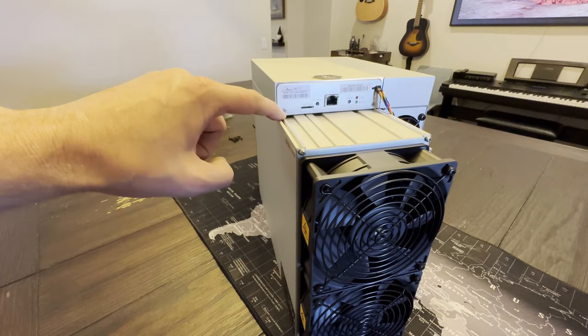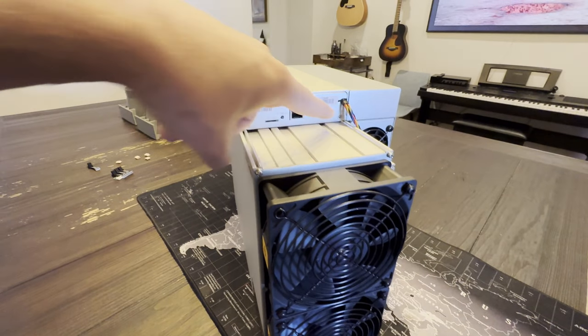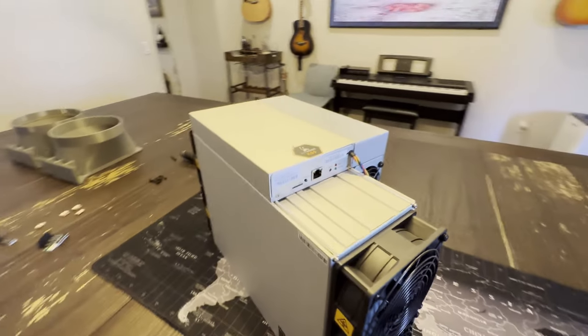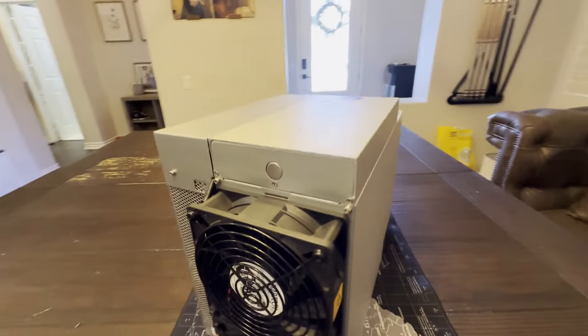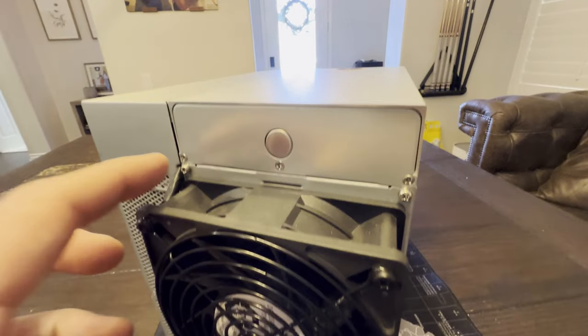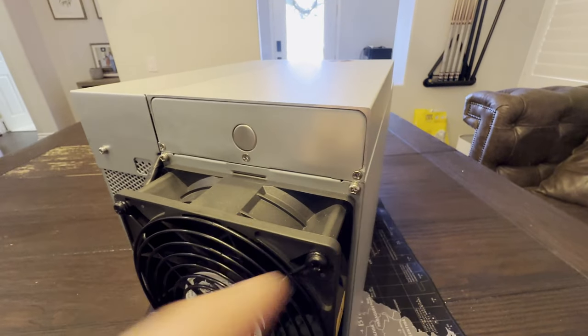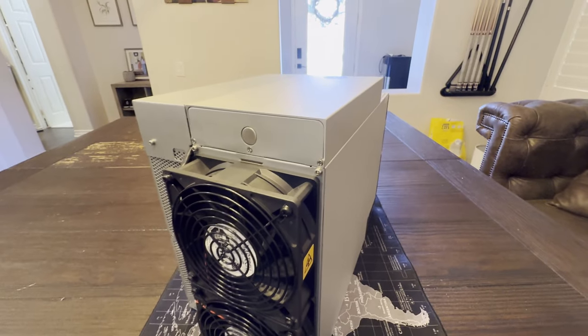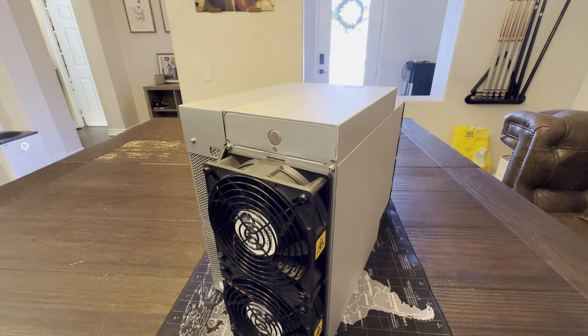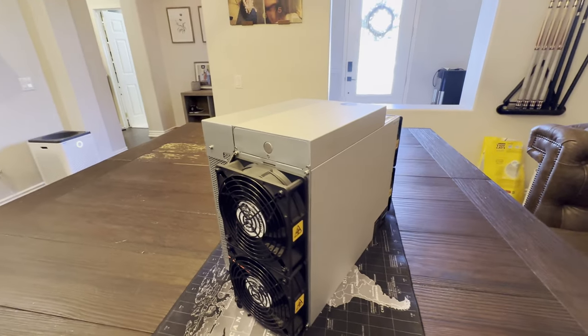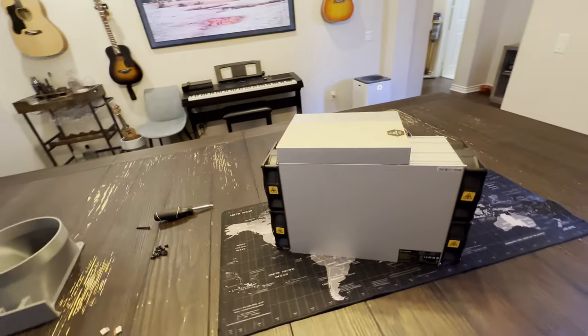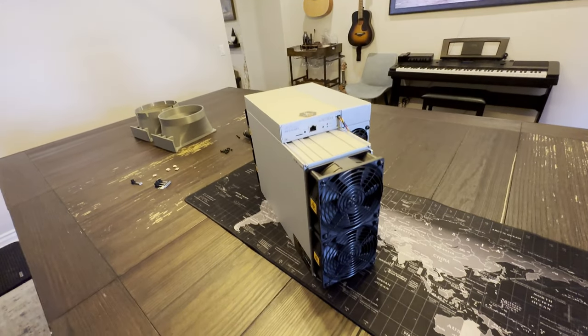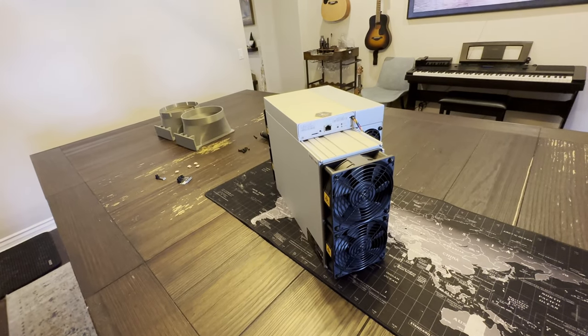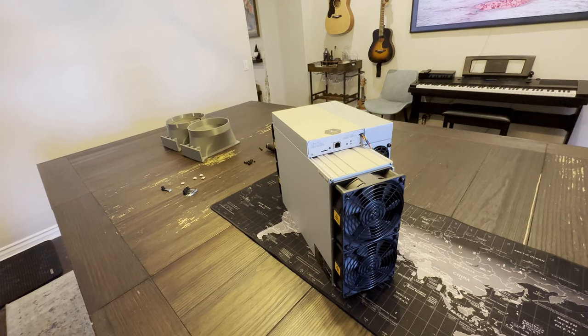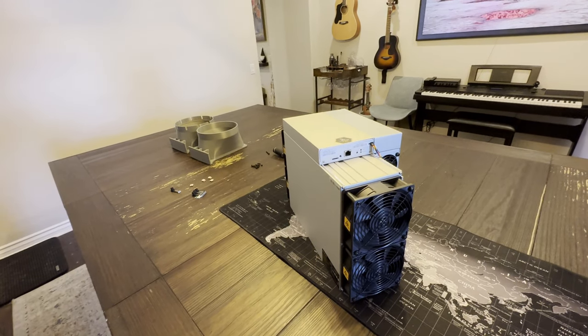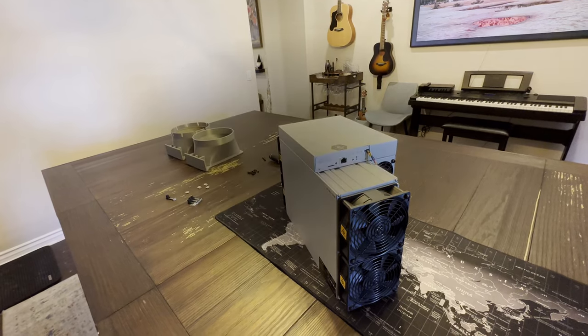What we've got to do is take out this screw right here and this screw over here. So there's two Phillips head screws in the front right there. And then on the other side, we've got three more Phillips screws. So again, one here, one here, one here. This is not a button, but it does in fact hold that faceplate on, so we've got to push it in to get that faceplate off. So what I'm going to do is take out those five screws, get this control board exposed, and then I'll show you guys exactly what those fan spoofer connections on the control board look like, and we'll figure out which one of these fan spoofers work. So let me get this control board opened up and we'll go from there.